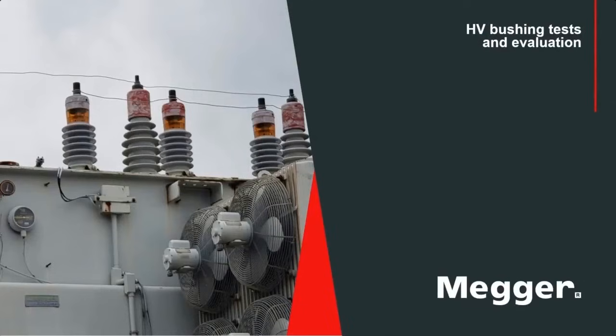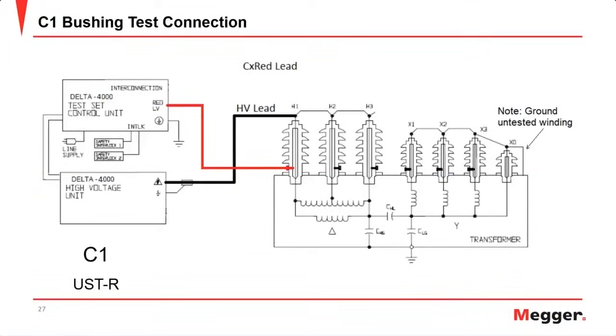And now, talking about the different bushing tests and the evaluation that we can perform. When you have these high voltage bushings, you will likely have a transformer that has at least two windings, with three to four bushings on the high voltage side and three to four bushings on the low voltage side. What we'll focus on for right now is testing a high voltage bushing on the primary side. The connection scheme on the screen shows that all of the high voltage bushings are shorted together.